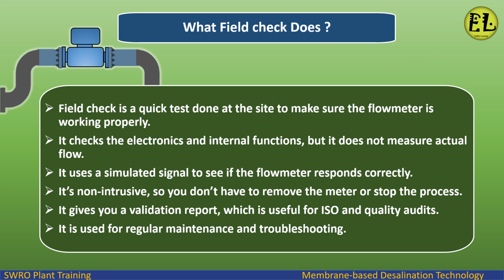What does a field check do? A field check is a quick test done at the site to make sure the flow meter is working properly. It checks the electronics and internal functions, but it does not measure actual flow. It uses a simulated signal to see if the flow meter responds correctly. It's non-intrusive, so you don't have to remove the meter or stop the process. It gives you a validation report, which is useful for ISO and quality audits. It is used for regular maintenance and troubleshooting.